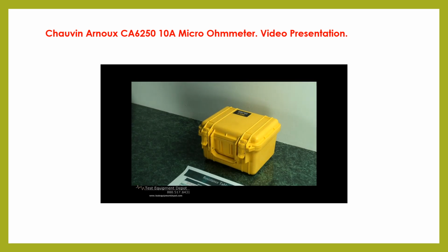There are two devices that are used to measure resistance: a micro-ohmmeter and an insulation tester or megohmmeter. These are often confused because they are both measuring resistance. In the case of the micro-ohmmeter, which we're going to cover today, we are effectively on the right-hand side of the decimal point. And here we see the decimal point, and as we get more and more sensitivity, lower and lower resistance, we see the engineering units change from centi, milli, all the way down to micro, which is 6 decimal places.